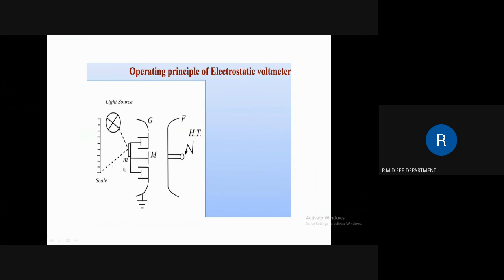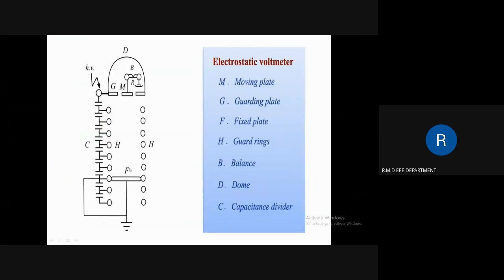Regarding the construction of this voltmeter, it consists of a moving plate M, a guarding plate G, and a fixed plate F, which is connected to the high voltage through a series capacitor. This is represented as a capacitance divider, and D is the dome used. B represents the balance of the bridge, and H represents the guard rings of the bridge.